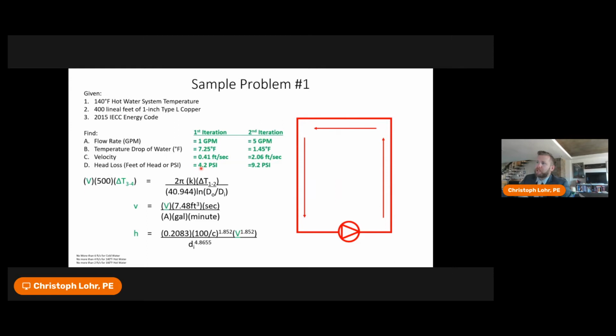Now, if we were to increase that flow rate because we wanted to reduce that temperature drop, let's say we didn't want that high of a temperature drop. We wanted to keep it as close as possible. And we increased that to 5 GPM and ran a second iteration with all those calculations, we would end up with a 1.45 degree Fahrenheit temperature drop for that 5 GPM, a 2 feet per second maximum velocity, and 9.2 PSI pressure drop.